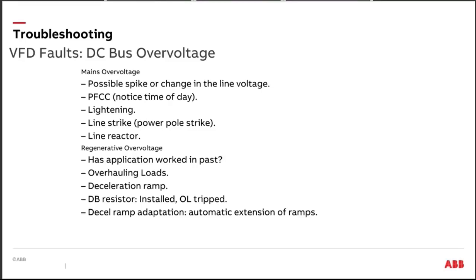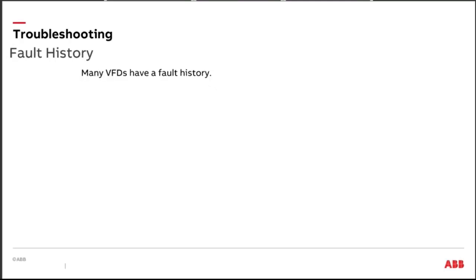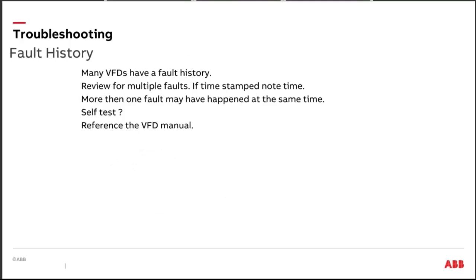In our drives, we can extend the ramp time by auto decelerating so that we watch the rate of the rise of the voltage on the bus and we start to extend that deceleration ramp. That might be something you want to set up inside the drive. Fault histories is a great place to go. Let's look and see what all is happening in the drive. Make sure that you're looking at all the faults. Fault history is great if you're coming in on Monday morning and you see that the drives are tripped on over voltage. Now you can look and see what the level is and see if it's consistent. See if I'm consistently tripping at 5:43 in the morning. Then I know right away, I need to be looking for power factor correction capacitor switching.